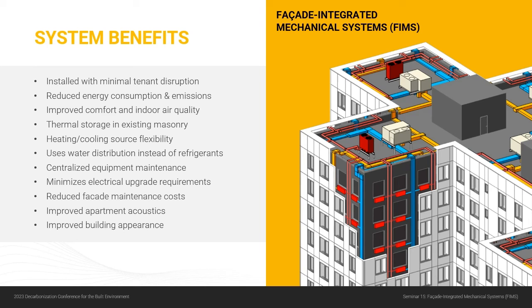And you're minimizing your electrical upgrade requirements. So by making the building more efficient, you most likely won't have to upgrade your electrical service, but also in terms of your distribution in the building, the only place that you need to run new power is to that rooftop equipment. You're not running new power to lots of little units all over your building. The power requirement of the fan in the FITU is so small, like in the 20 to 30 watt range, you can even power those with low voltage wiring.